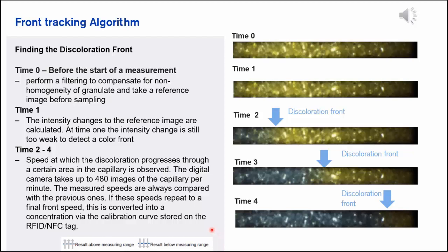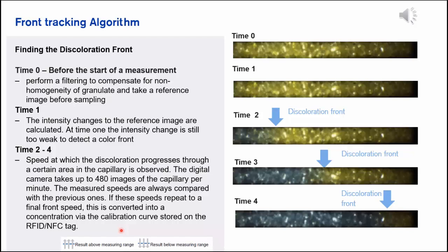And that is the means by which we can save the customer a bit of time in the event of a very low concentration. Conversely, and even more importantly for my opinion, is this option. Let's say you were taking a benzene measurement and you expected the concentration to be rather low and in reality, due to whatever condition was presiding at the time, it was much higher than you anticipated. The device will literally within seconds interpret that with a discoloration in the capillary and very quickly stop the measurement and present this in the display so that the user have an early warning that the concentration was perhaps much higher than they had anticipated. And I think that's a significant advantage particularly when dealing with some of these carcinogens.